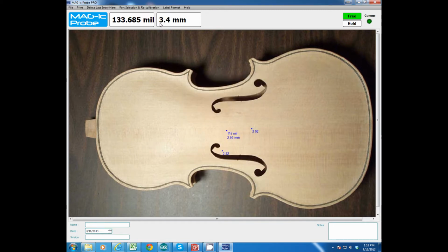So when I click now, you'll see that the millimeters has gone up a little bit, and when I click now, that 0.5 has now been added to the actual reading over there. So again, if you want to add an offset, preferably do it in the measuring range that you'll be measuring. So when you're comparing to some other type of measuring device and you want to set them both the same, do it in the range that you're measuring. So don't do it in the 10 millimeter range if you're measuring a 2 to 3 to 4 millimeter instrument.